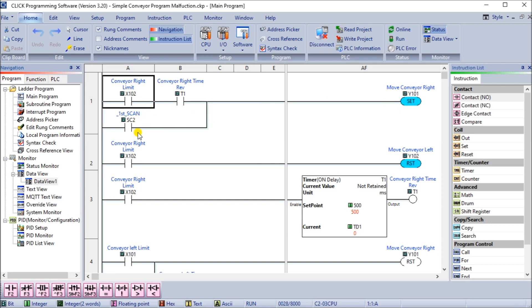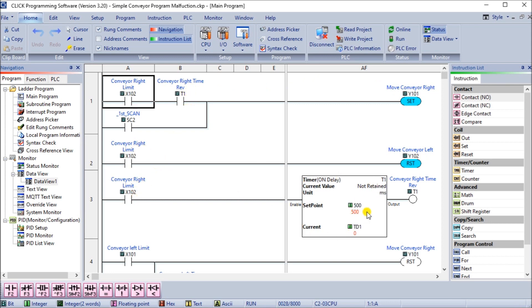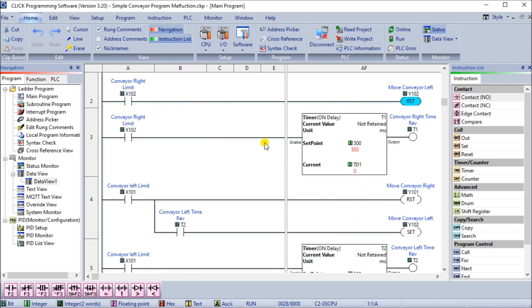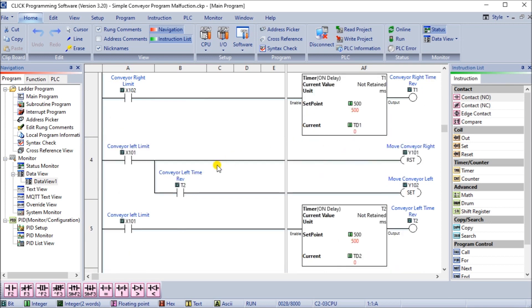Then when we have a limit switch, which is X102, the right limit switch, or the right sensor switch, it will stop the conveyor moving to the left, reset that, and it will start a timer. That timer times up for 500 milliseconds, or half a second. It activates this, and then we move it to the right again. As we go to the left sensor, we'll hit the move to the right. It turns off. We wait for a time period to then set move to the left. That time period again is 500 milliseconds, which is half a second.